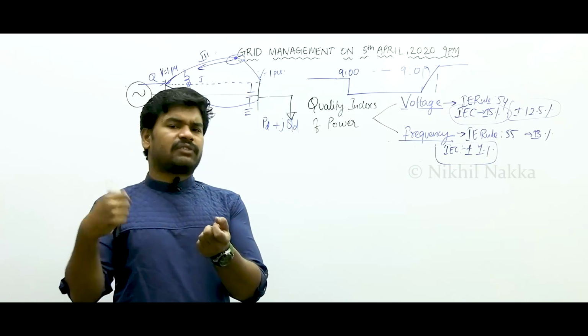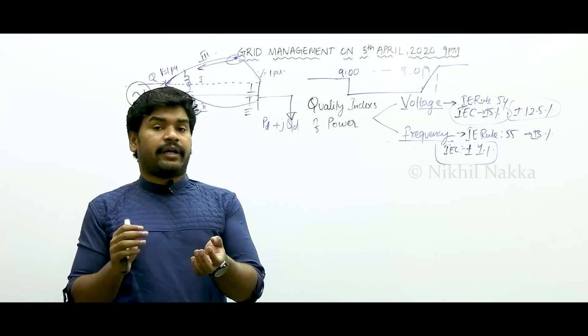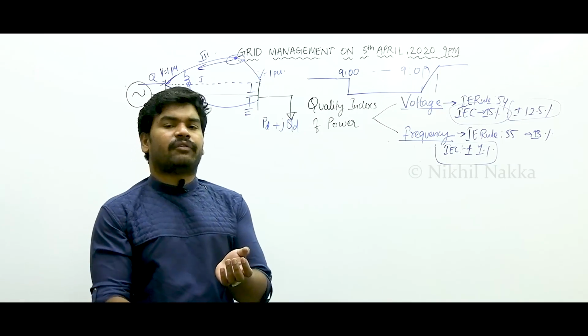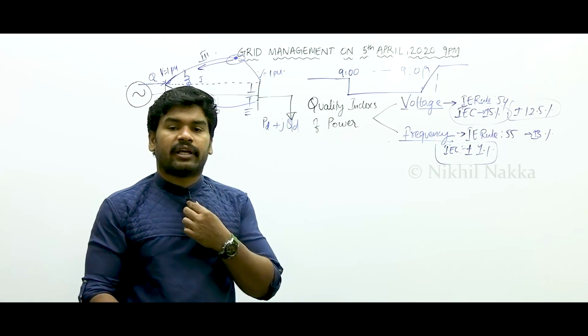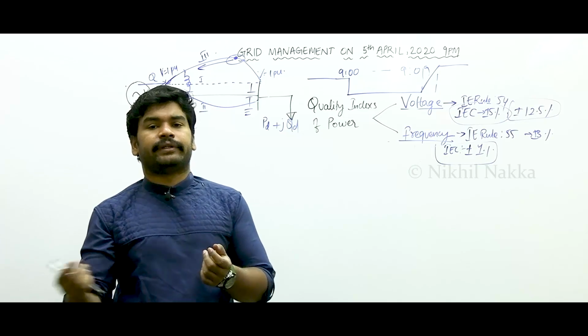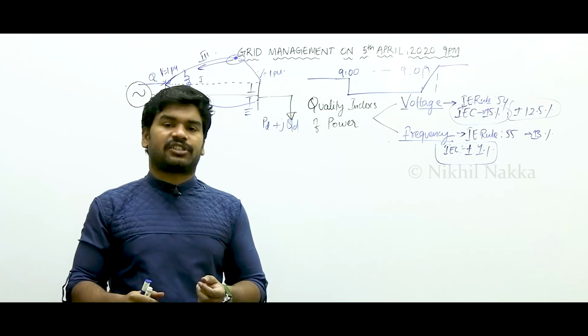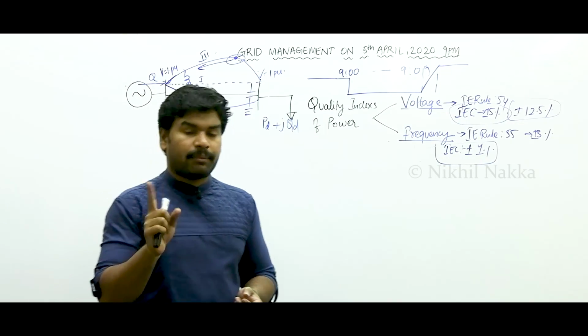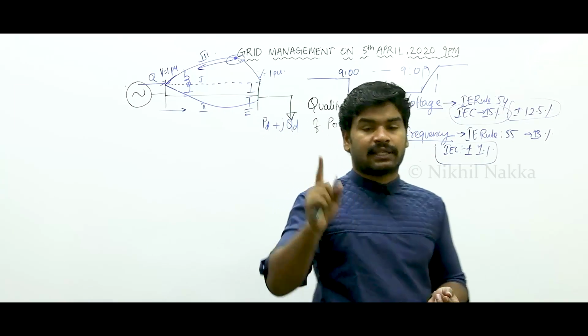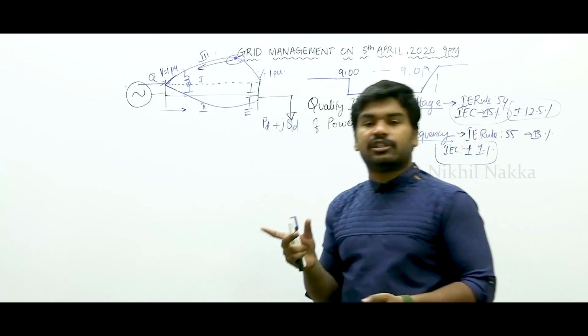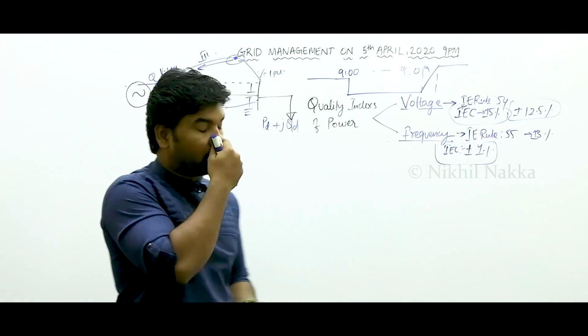Reactive power drops, voltage will drop proportionally, no problem. But if reactive power suddenly drops, if it sharply drops, there will be a sharp rise of voltage, a high surge. Here the problem is not with the magnitude, here the problem is d by dt, rate of change of power. Understood? I hope your doubt is clarified.